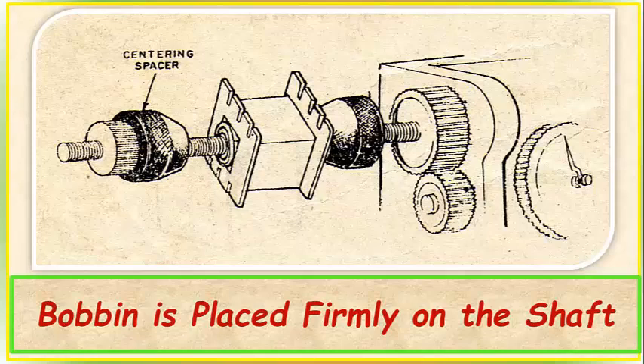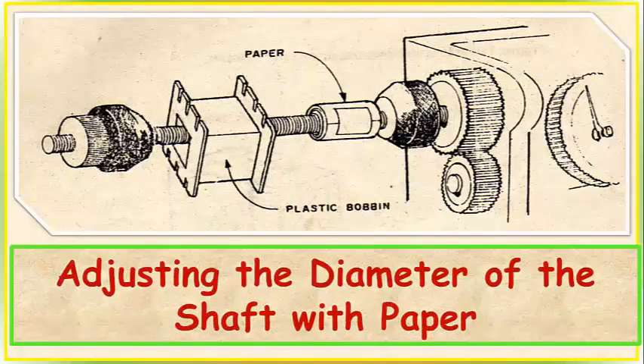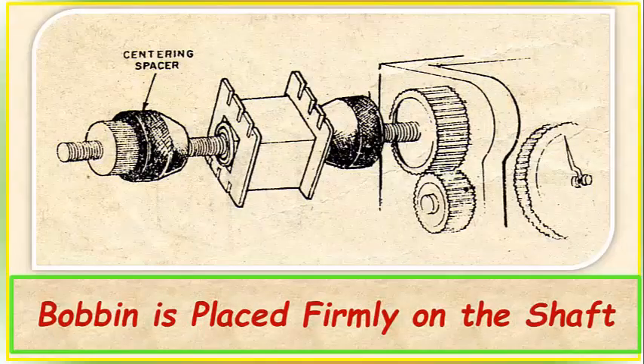In case the centering spacer of the winder fits inside the bobbin, there is no need to add paper to the shaft to center the bobbin. So this is how to adjust the diameter of the shaft with the paper. Then, the bobbin is placed firmly on the shaft. In winding coils, preformed bobbin has slots on the sides to hold the leads of coil. Secure external leads of the coils in these slots temporarily.